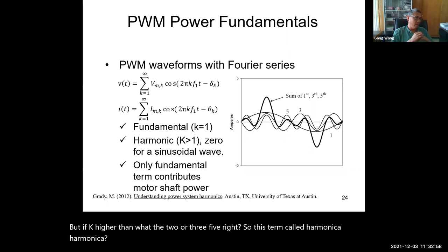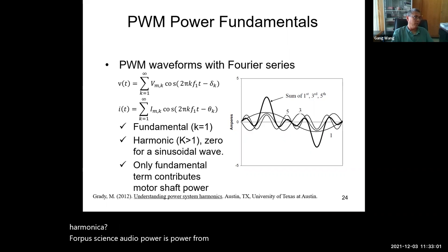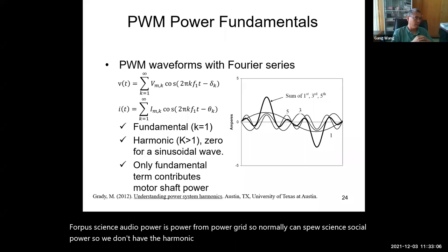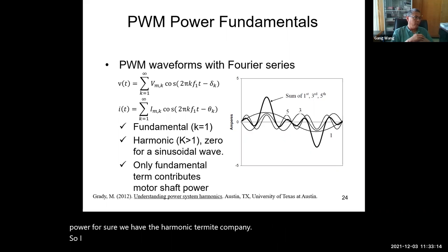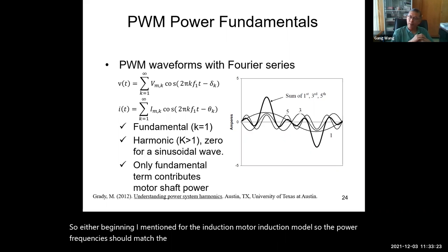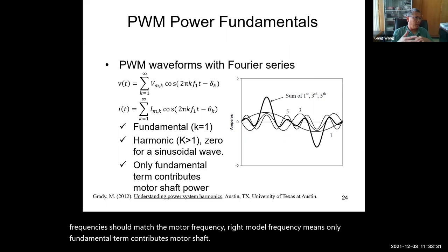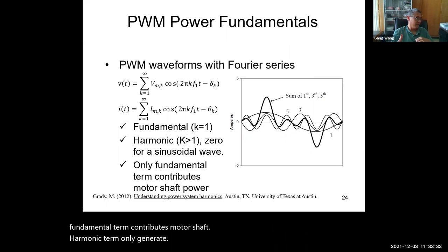For pure sinusoidal power, the power from the power grid, we don't have the harmonic terms; the harmonic term is 0. But for PWM power, for sure, we have harmonic terms. At the beginning, I mentioned that for the induction motor, the power frequency should match the motor frequency. It means only the fundamental term contributes to the motor shaft. The harmonic terms only generate heat loss. This is one conclusion.